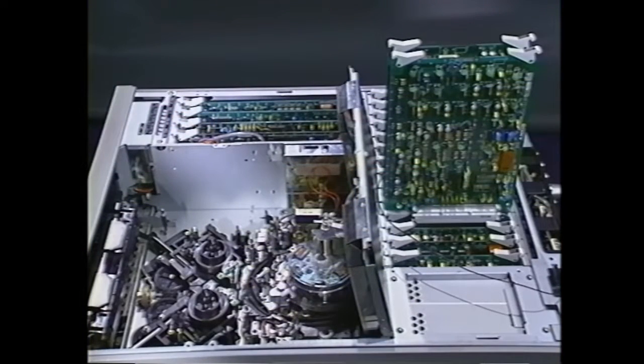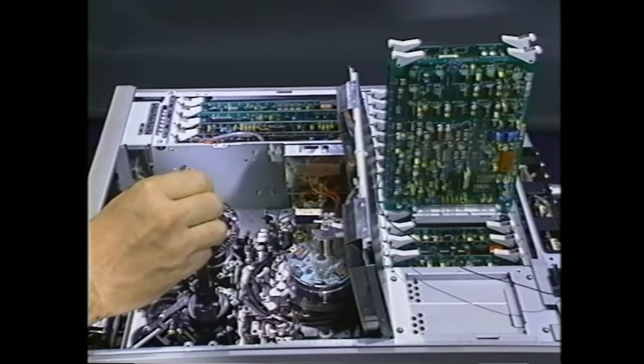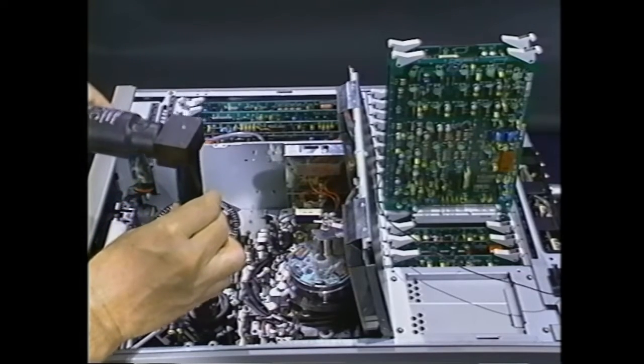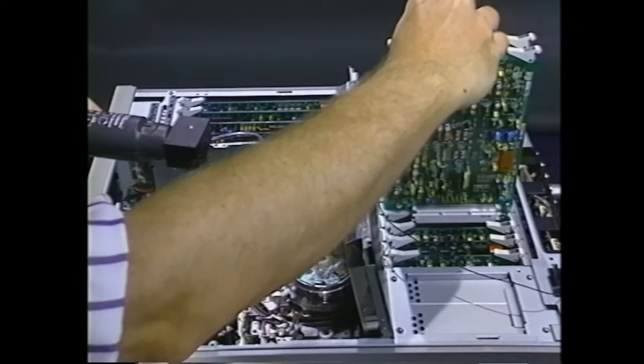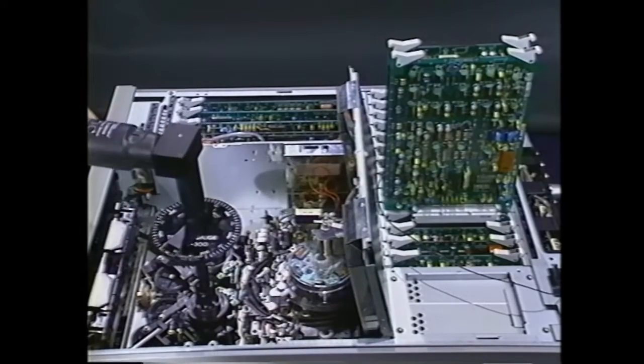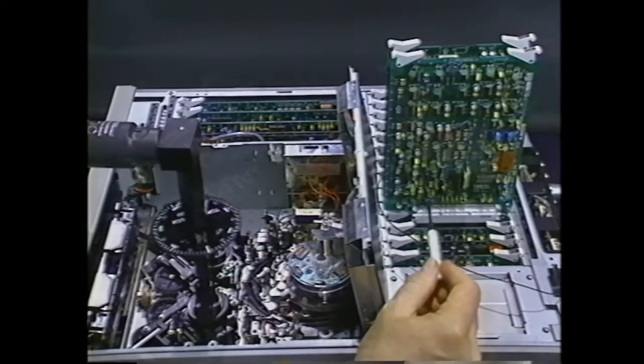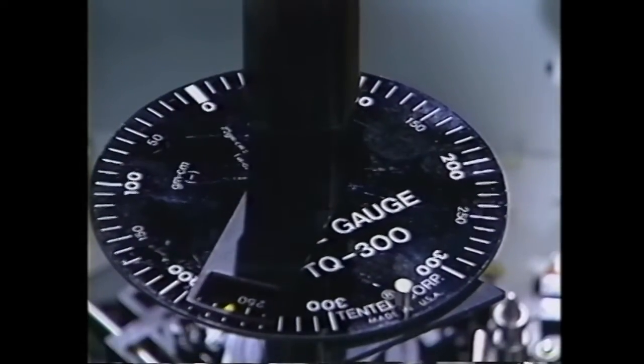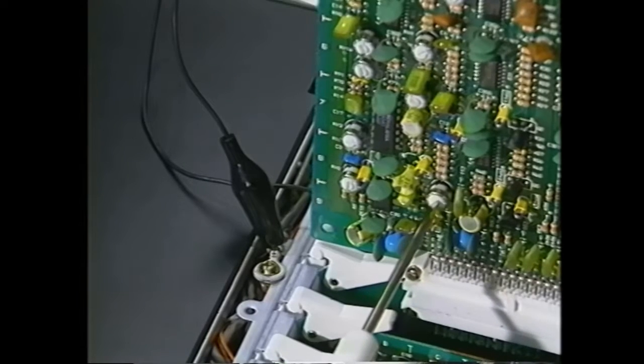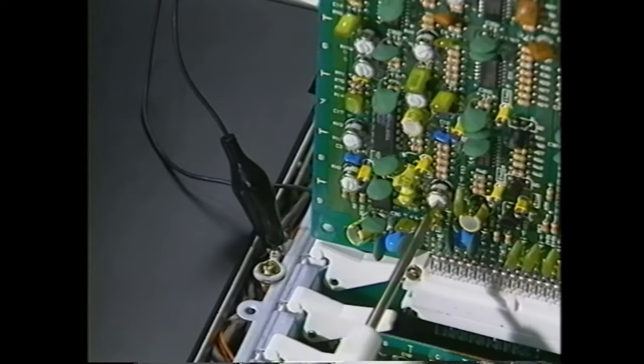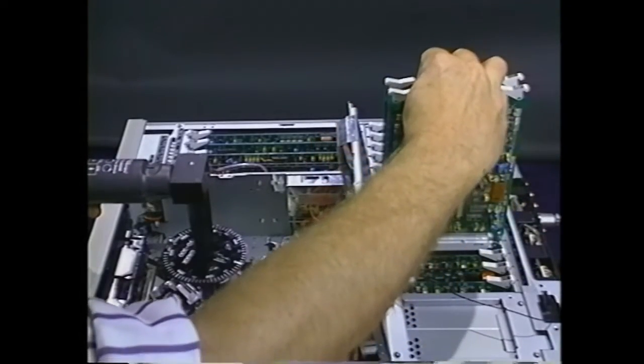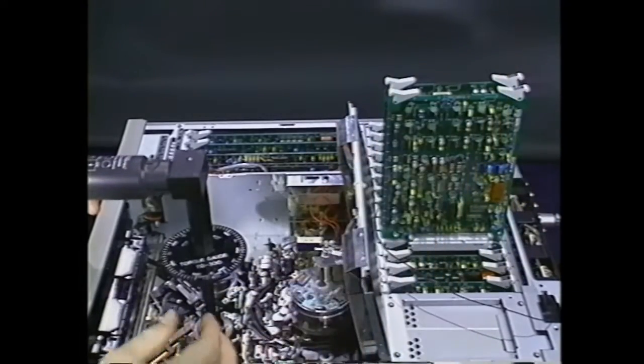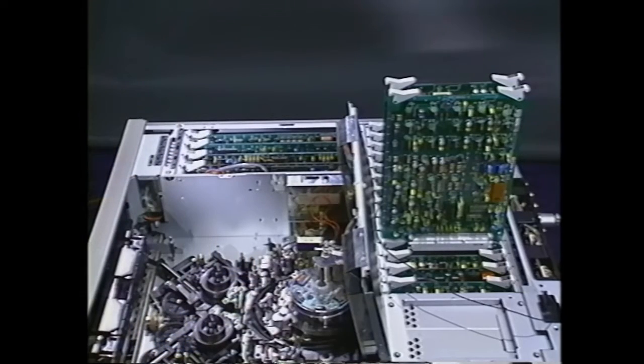Next, place the torque gauge over the take-up spindle and flip bit 1 to the off position to restore torque to the reel tables. Again, compare the non-rotating torque with the counterclockwise rotating torque. Both should be within 10 grams of the 250 gram-centimeter torque specification. Adjust RV13 on the SV83 board if adjustment is required. Flip bit 1 on S101 to remove torque from the spindles and remove the torque gauge. This completes the torque measurements, so we can now return the transport to normal operation.